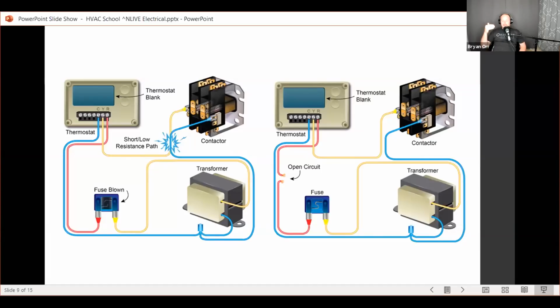But the actual voltage rating on a fuse, that is a rating that has to do with the point at which an arc can go across it. So you can use a higher voltage. And he's asking me how much higher. Again, in most cases, they're going to be very close, because they're going to be the same general design. So it's going to be rare that you're all of a sudden going to have some fuse that looks exactly like another fuse that's going to fit, that's going to be a significantly different voltage.